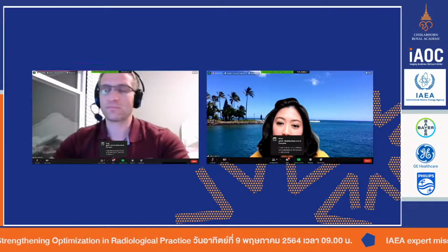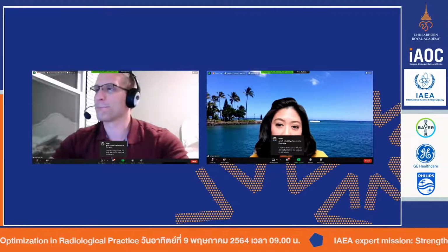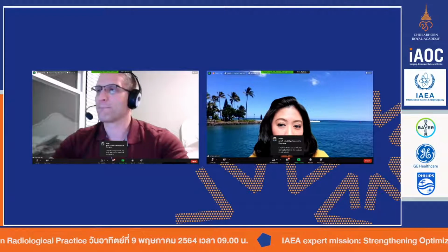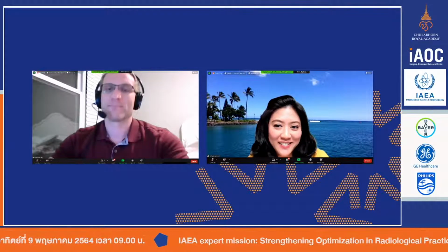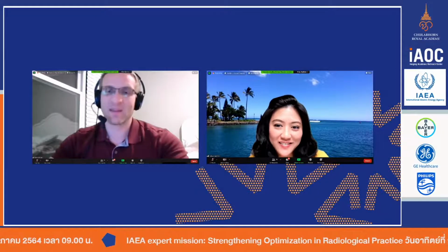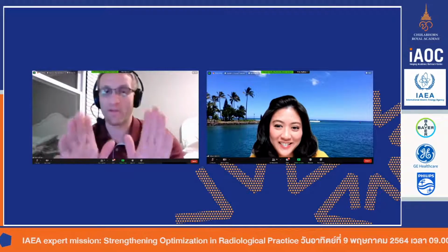Yeah. And right now for the DI deviation index, do you recommend plus and minus 3, or can we go up to plus and minus 10 when we look at these things? Historically, it was plus or minus 3. But what we found out was that +4, +5 was still okay. We found it was generally okay all the way out to plus or minus 10.